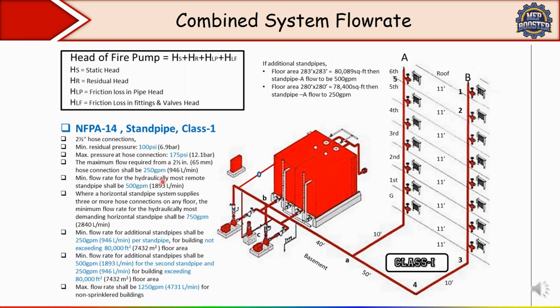And the important thing which I want to show you is at this point. The minimum flow rate for the hydraulically most remote standpipe shall be how much? 500 GPM. The hydraulically most remote standpipe means the standpipe which is farthest from the pump. So if you see in this image, we have two standpipes, one here, but the farthest one is this B. So the minimum flow rate for the hydraulically most remote standpipe shall be 500, and for any additional standpipe it shall be 250 per standpipe. But one condition is given for the additional standpipe 250: for a building not exceeding 80,000 square feet floor area. If the building exceeds 80,000 square feet floor area, the minimum flow rate for the second standpipe shall be 500, and for the remaining ones 250.